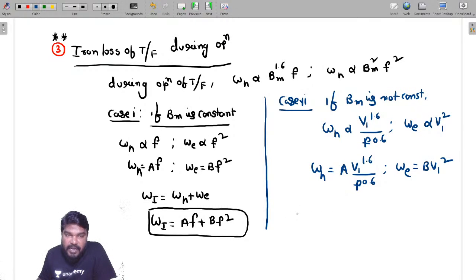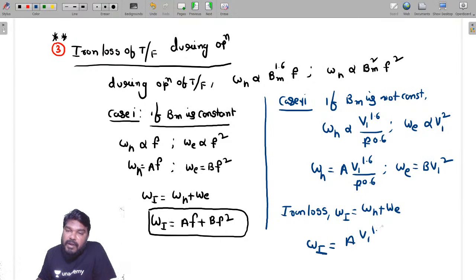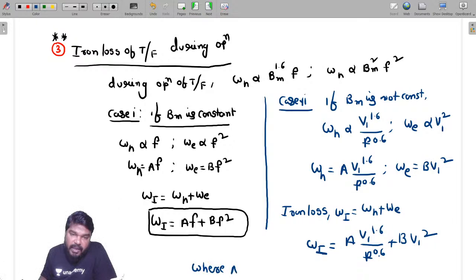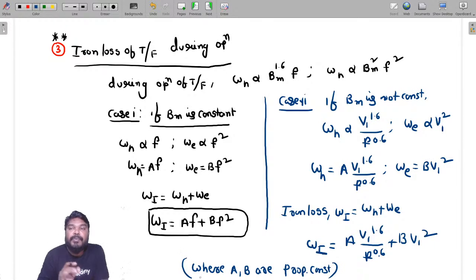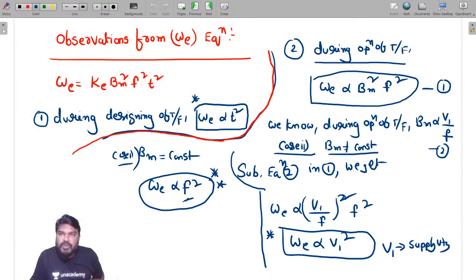Now simplify to calculate the iron loss of the transformer. Iron loss Wi is equal to WH plus WE. Therefore iron loss is equal to A into V1 power 1.6 divided by F power 0.6, plus B into V1 square. Here A and B are the proportionality constants. So that completes the iron losses during operation of the transformer. Joseph, all of it clear? Here I have taken simply the case 1 point of view. During the operation, this is the formula.